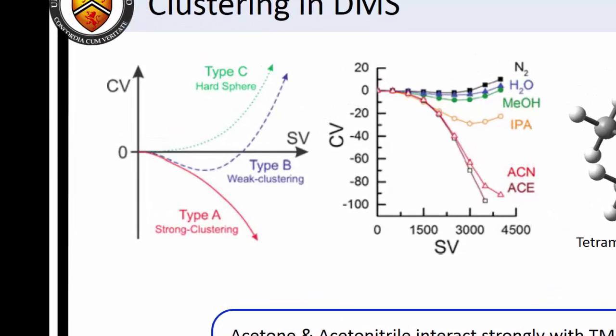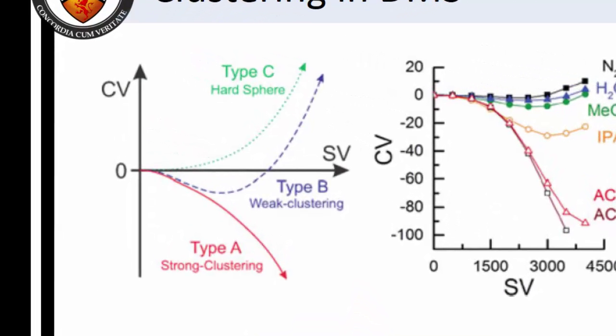Ion transmission through a DMS cell is tuned via two parameters: an asymmetric separation voltage that is composed of two sine waves and a DC compensation voltage. By monitoring the optimal conditions for ion transmission as a function of SV and CV, we generate what is known as a dispersion plot.